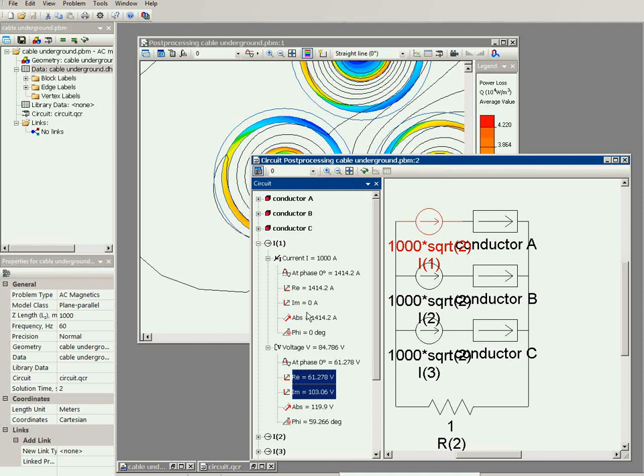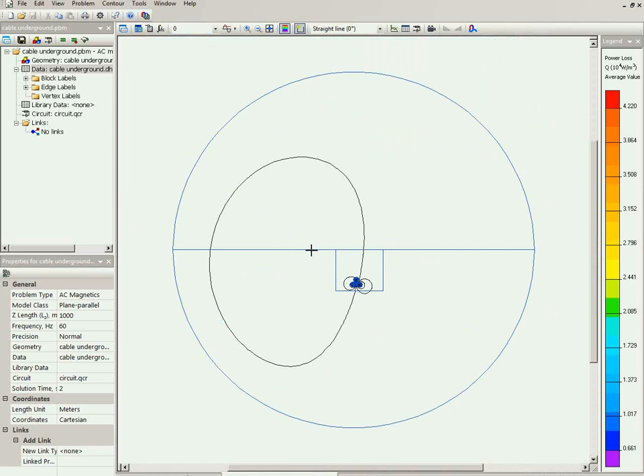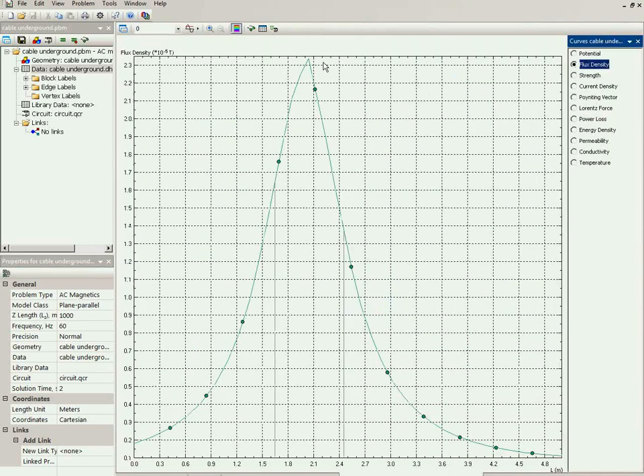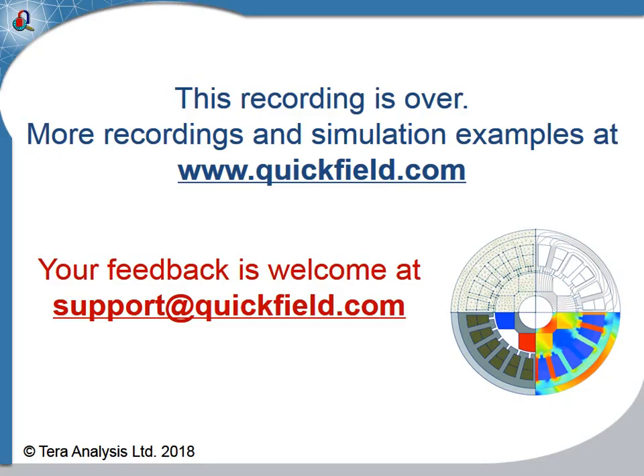We can also find the impedance of each conductor. We know the current — real and imaginary parts — and we know the voltage — real and imaginary parts. If we divide the complex voltage by the complex current, we can find the impedance: the resistance and inductance of the cable, and the same for the screens. We can also find the electromagnetic field generated by this three-phase cable system. For example, selecting the ground surface and switching to an XY plot of flux density, we can see that just above the cables the magnetic flux density is about 23 microtesla.